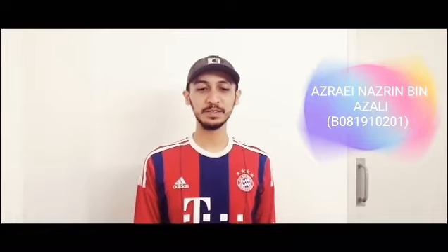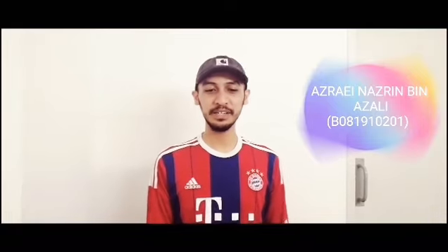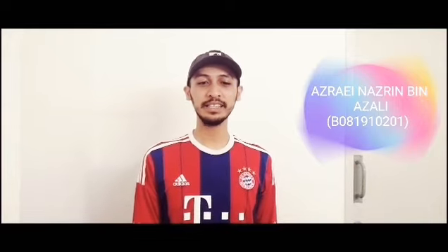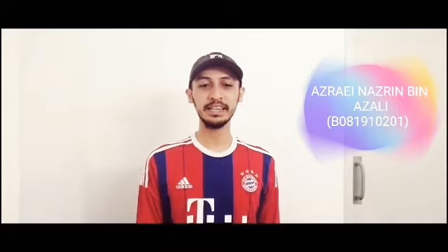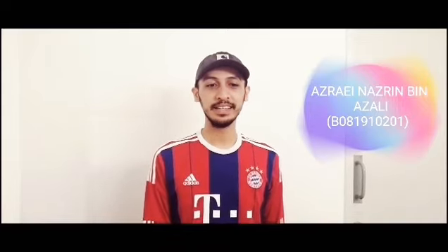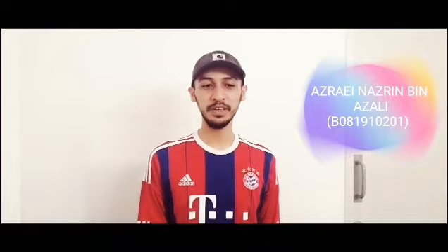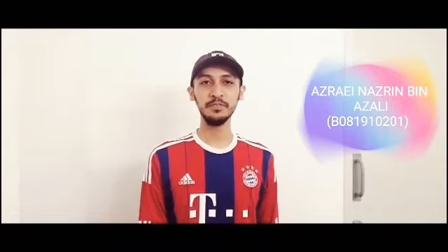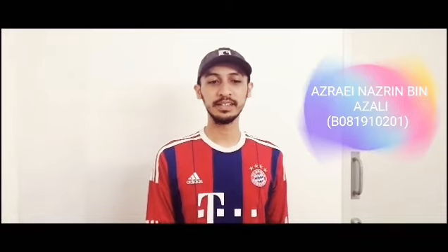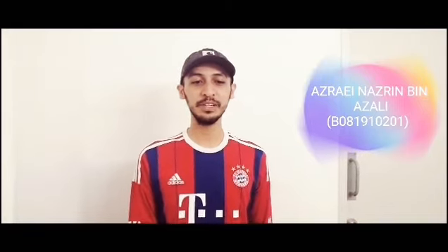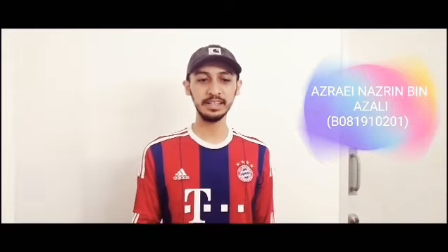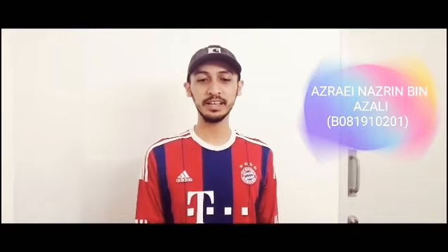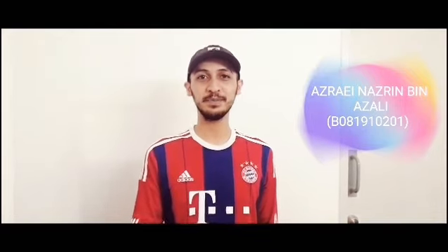Firstly, I want to tell you about the first continuous level measurement, that is the ultrasonic level sensor. What is an ultrasonic level sensor? Ultrasonic level sensors are used for detecting the levels of various liquid substances and bulk materials as well. They operate by emitting acoustic waves at a frequency range of 20 kHz to 200 kHz. The sound waves are then reflected back to a transducer. The response of an ultrasonic sensor is influenced by pressure, turbulence, moisture and temperature. In addition, the transducer is required to be mounted appropriately to obtain a better response.